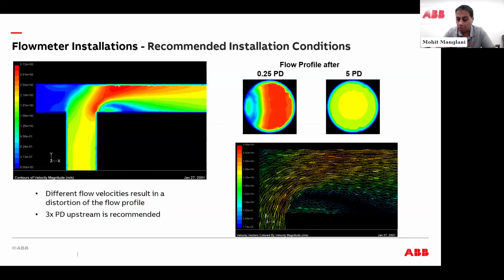This is just to show you that if I install around a bend, this is my flow profile here, at 0.25 piping diameters. But if I have 5, you can see I have perfectly laminar flow. So this is a nice representation of what good piping looks like and how it affects your flow profile.